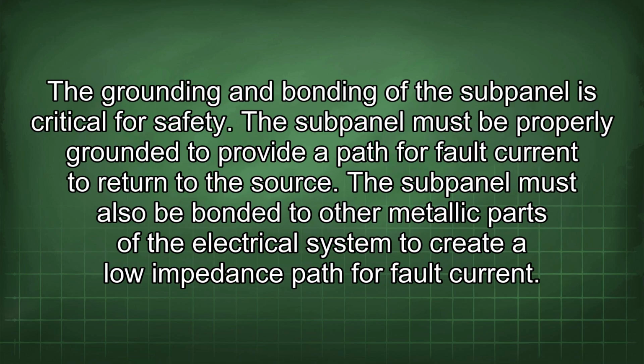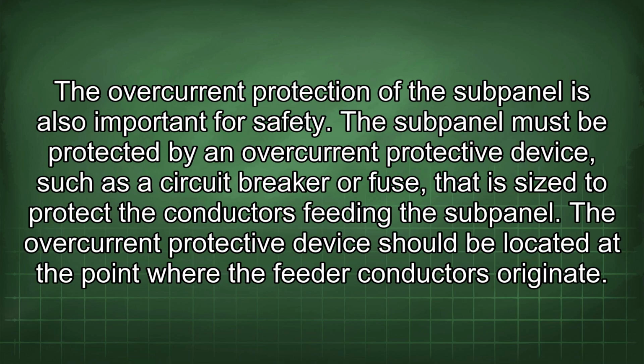The grounding and bonding of the subpanel is critical for safety. The subpanel must be properly grounded to provide a path for fault current to return to the source. The subpanel must also be bonded to other metallic parts of the electrical system to create a low impedance path for fault current. The overcurrent protection of the subpanel is also important for safety.